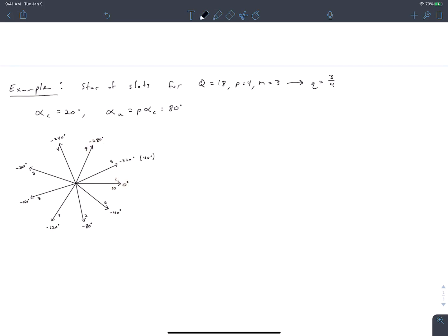We can finish going around the star of slots. We notice that in the fractional slot winding, slot phasors don't always appear in the same order on the phasor diagram. In an integral slot winding, the next slot clockwise from slot 1 would have been slot 2. But here, the next slot clockwise from slot 1 is slot 6 — the phasor for slot 2 skipped one position. This is another fundamental difference from an integral slot winding.